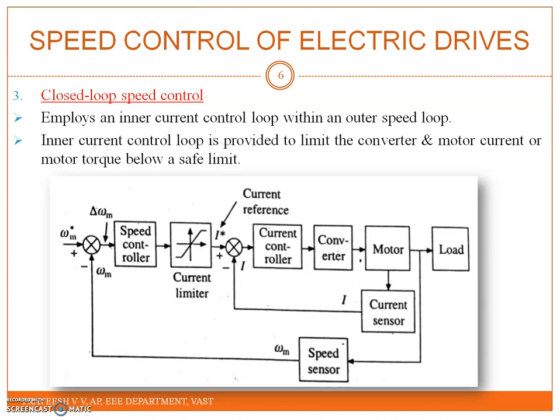When close to the desired speed, the limiter desaturates and steady state is reached at the desired speed at a current for which motor torque equals load torque. A decrease in reference speed produces a negative speed error, and the current limiter saturates and sets the current reference for the inner loop at a value corresponding to the maximum allowable current. Consequently, the drive decelerates in braking mode at the maximum allowable current. When close to the required speed, the current limiter desaturates and operation transfers from braking to motoring, and the drive settles at the desired speed.